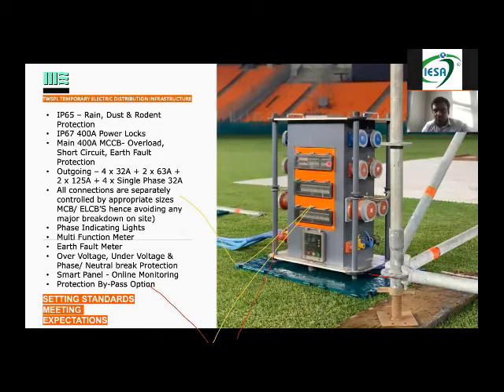If you have 20 units of AC and one AC gets faulty, only one MCB will trip. It is easier to replace one AC than to have everything go off and then go hunting for what went wrong, taking out wires and so on. So this is as per the Indian Electricity Rules, that everything needs to be separately controlled.